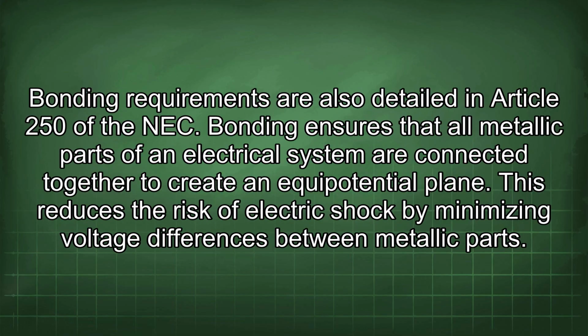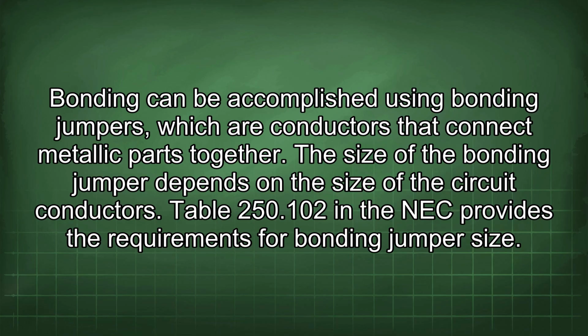Bonding requirements are also detailed in Article 250 of the NEC. Bonding ensures that all metallic parts of an electrical system are connected together to create an equipotential plane. This reduces the risk of electric shock by minimizing voltage differences between metallic parts. Bonding can be accomplished using bonding jumpers, which are conductors that connect metallic parts together. The size of the bonding jumper depends on the size of the circuit conductors. Table 250.102 in the NEC provides the requirements for bonding jumper size.